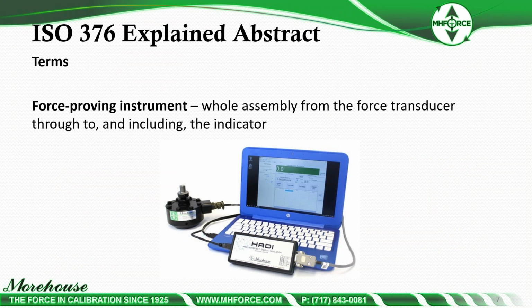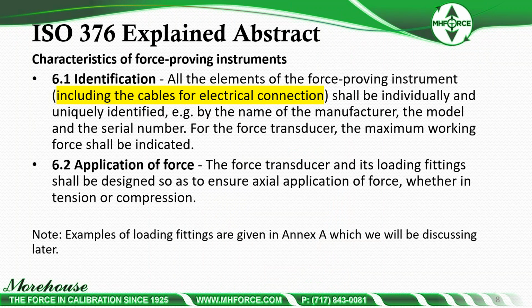What is a force-proving instrument? It's a whole assembly from the force transducer through to and including the indicator. So it's the whole system. I always recommend that, if you're using a device with an indicator, you send everything in for calibration. You send the device with the indicator, with everything you're using, and it can be calibrated as a full system. This includes cables. And ISO does an interesting job. I've seen this in the ISO 376 standard and also in the Australian standard: characteristics of force-proving instruments.